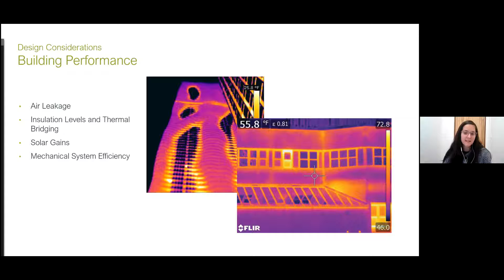We're not putting added load on our geothermal system. At 575 Princess, we actually moved away from a window wall cladding system, which is typical on a lot of multi-unit residential buildings from developers. We've got framed insulated walls, a glazing ratio I think a bit lower than the 40% mark, and our building worked out to be heating dominated. To account for that, we upsized the domestic hot water boiler to allow for supplemental heat injection if needed.